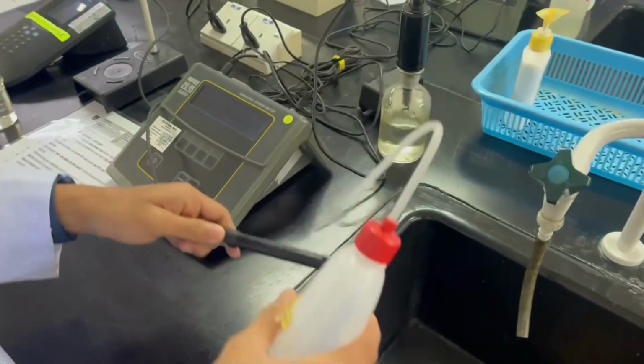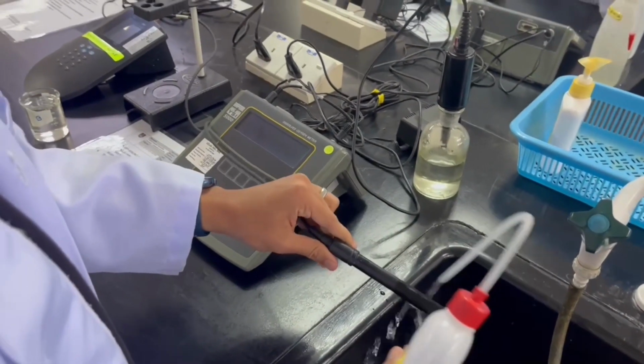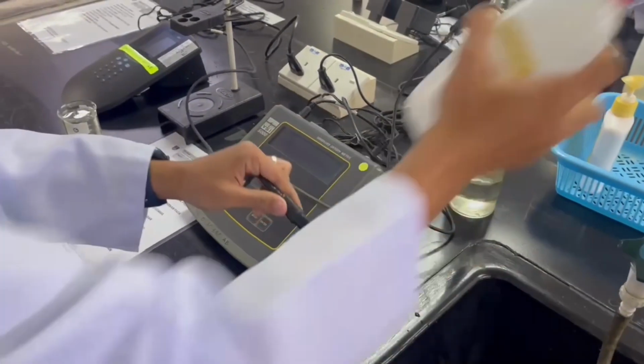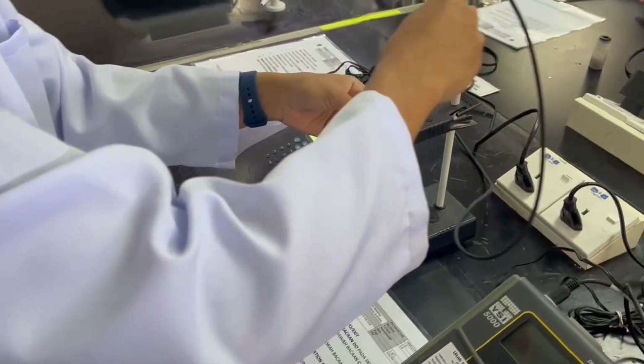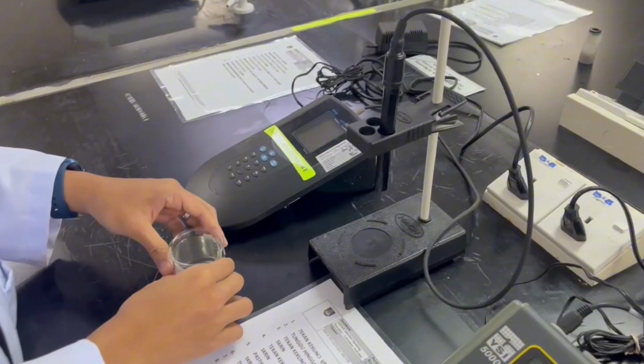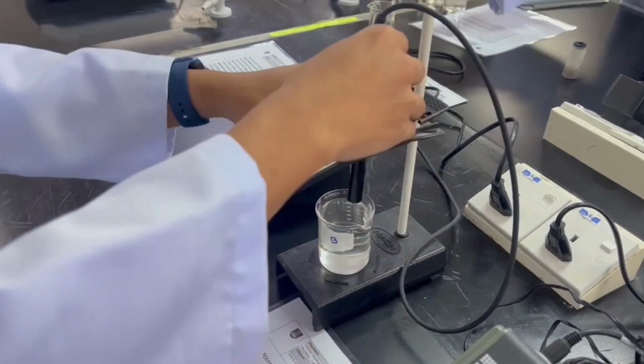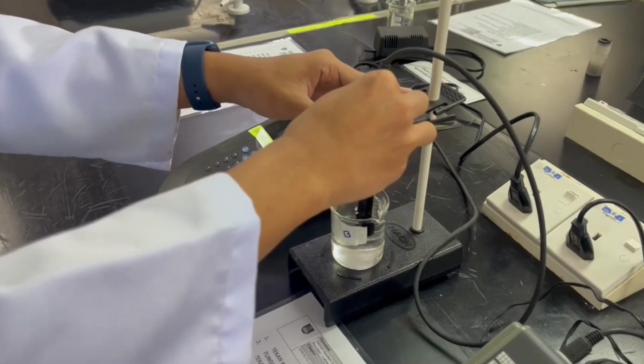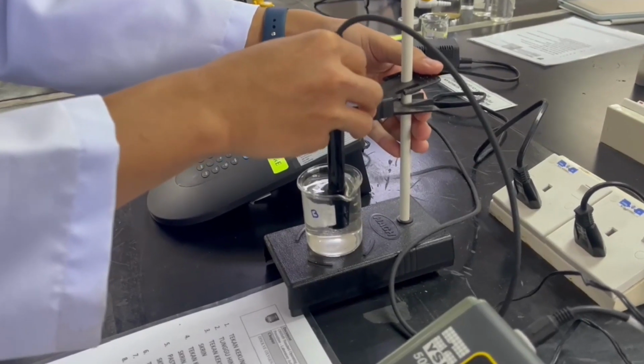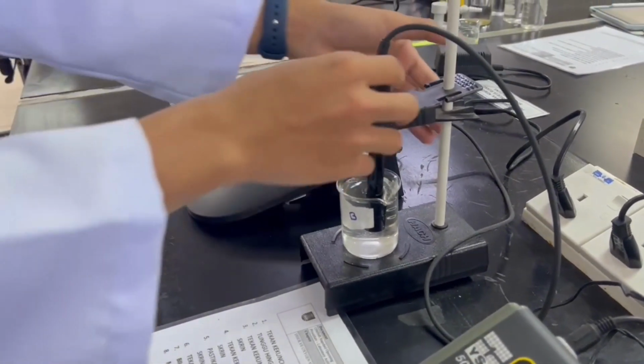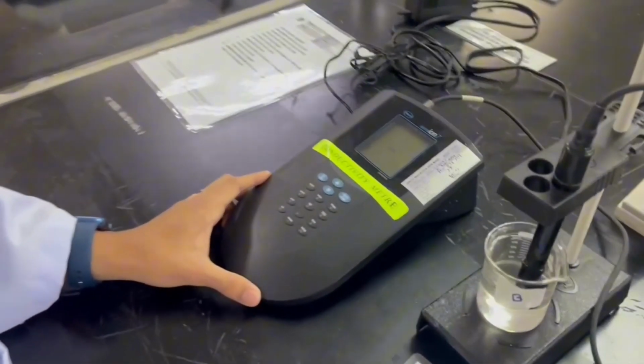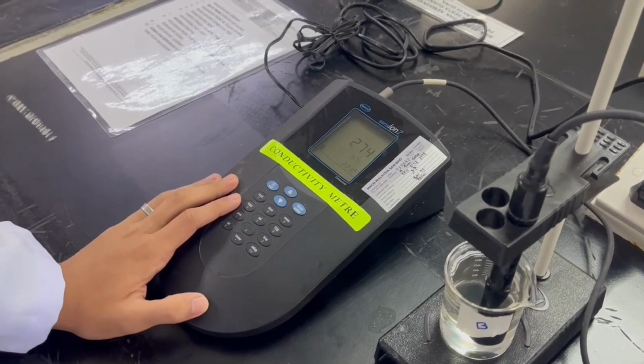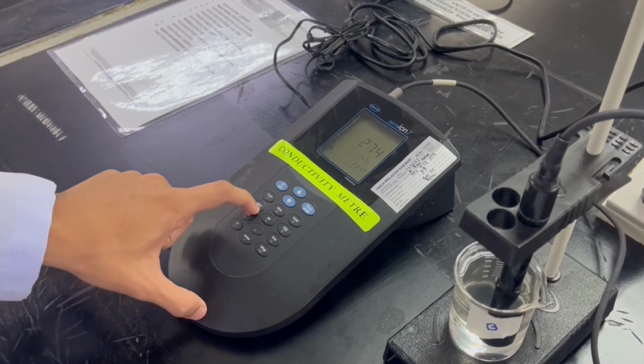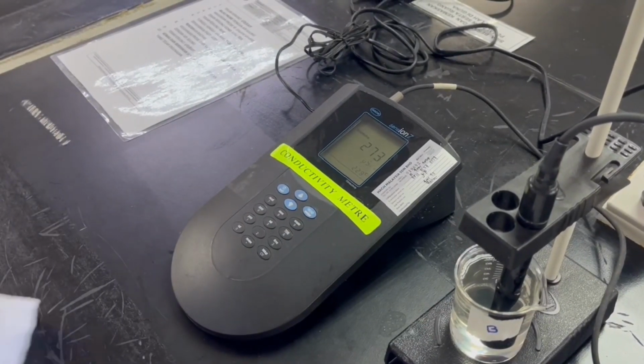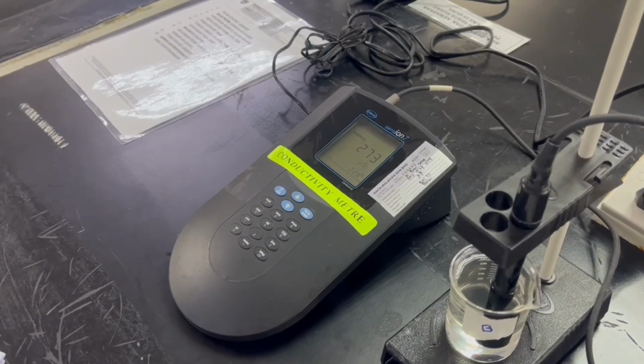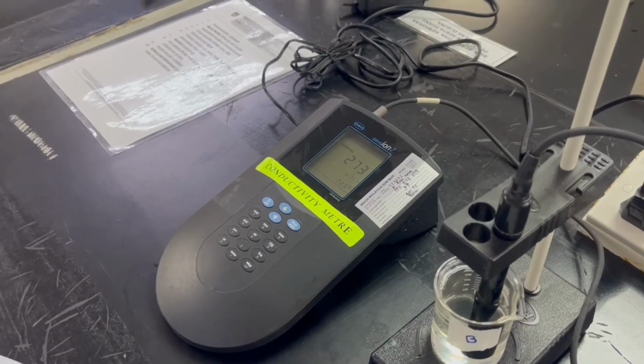After that, rinse the probe with distilled water and shake off the extra drops. And then we take the beaker, slowly put it below the probe, and slowly push the probe into the water sample. Make sure the probe is in the middle of the beaker. Don't let it touch the sides or bottom of the beaker. And then we turn on the meter, push the conductivity button, and push the read button. Then we wait a few seconds until the number on the screen stabilizes.